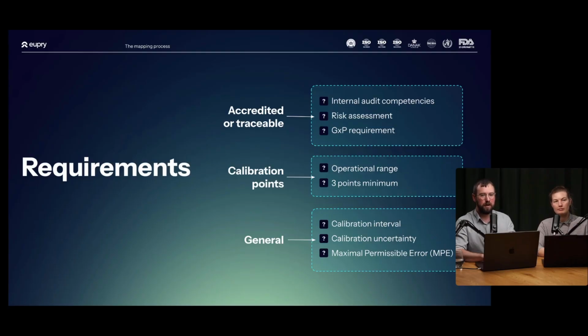So we just have another question here from Sunari. We always have a calibration expiry date that has to be done again after a certain deadline by the calibration third party. How do they determine the timeline? What are the parameters in which it is decided? For equipment that has 1 year calibration validity, why not 6 months or 2 years? Now, this is super interesting because the calibration is actually just a point in time measurement. So how can it have an expiry date? That's a really good question, and we're actually going to go into detail with this.